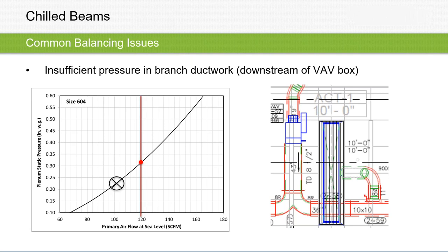With oversized ductwork, if you have too large of a diameter, the feet per minute is going to drop. You're going to have a lower velocity in that ductwork, and that's going to make taking your traverse a little more difficult. You're probably going to see more noise in that traverse, and what we found with those traverses is that if you have a lot of noise, we tend to read the higher numbers and maybe be a little bit generous with the CFM.